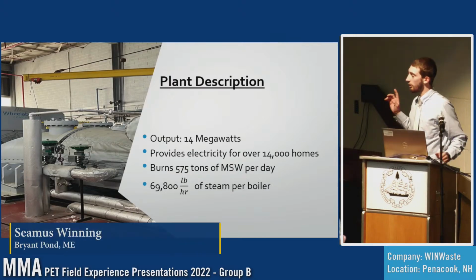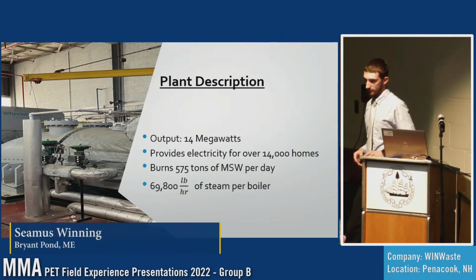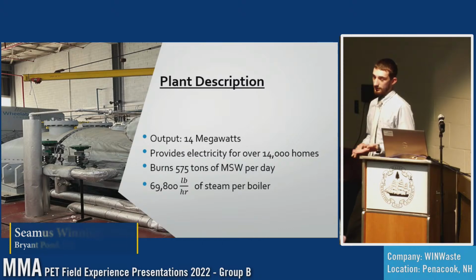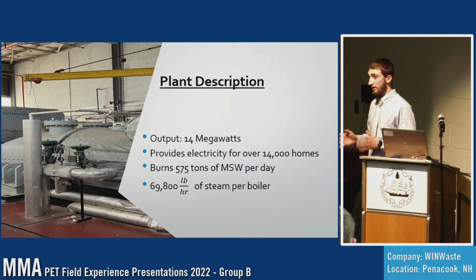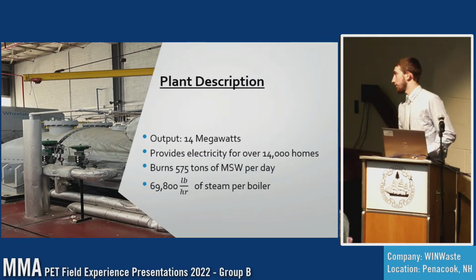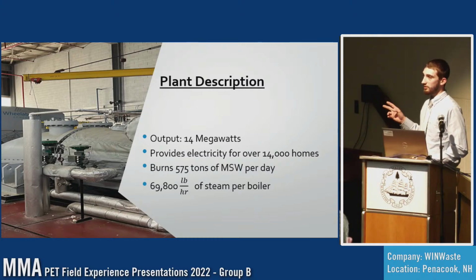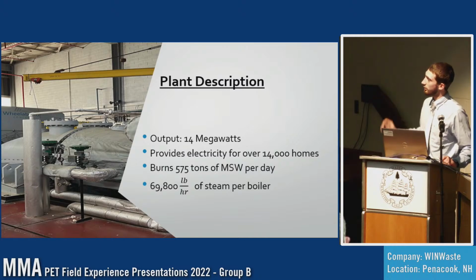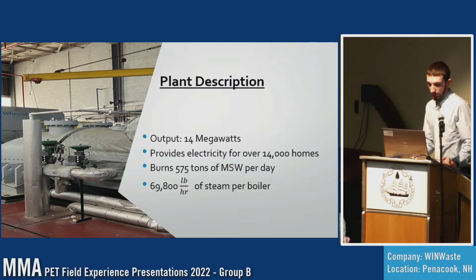We were a base load power plant that output 14 megawatts. It was a mass burn trash plant, and we took about 575 tons per day of municipal solid waste in to burn. We had 2 B&W boilers that each put out 69,800 pounds per hour of steam to a Dresser Rand 16-stage turbine generator.